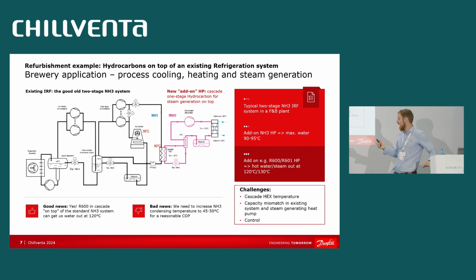balancing of the load. And then, why butane? There are various hydrocarbons. Well, we have tried to investigate a few. Butane is a good one, as it has a reasonable displacement required versus the next step, which would be pentane, which has a higher critical temperature, a bit better COP. However, you need 2.5 times bigger compressor. So bigger compressor, bigger components, bigger money, no business case. These are a few of the considerations.